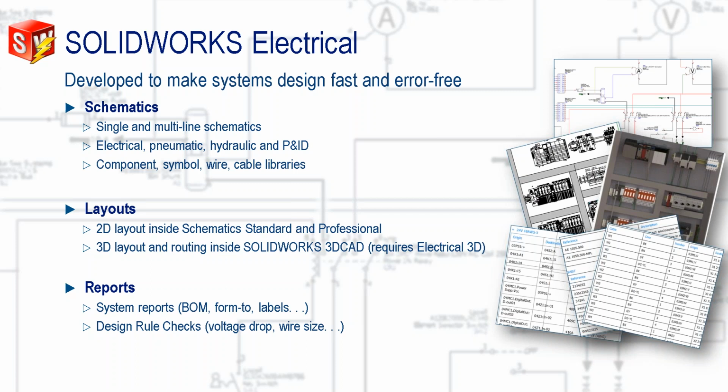Yes, we have purpose-built tools such as insert symbol and insert wire, but the ROI at first can be felt in the reports, because if you're using a traditional CAD tool, you're more than likely using an external program to generate those reports. We automate that process. All of the metadata is contained within the schematics. We extract that information and compile it into various tables and report types such as bill of material, wire from to, and wire labels. In addition, we also have a different type of report called a design rule check.